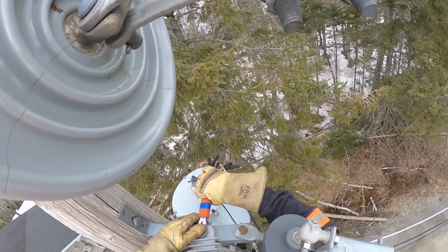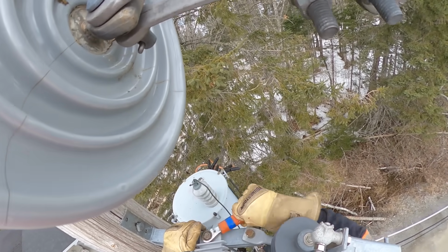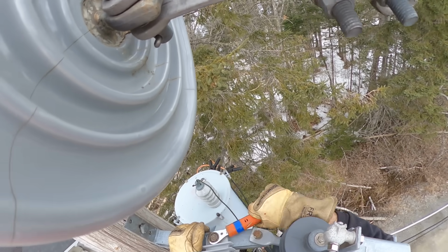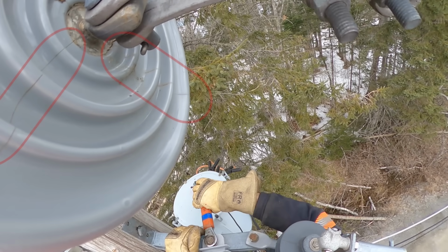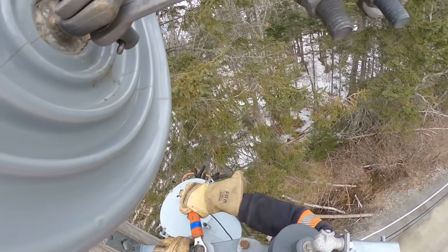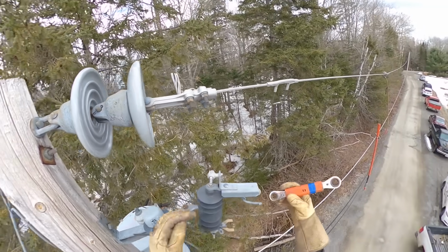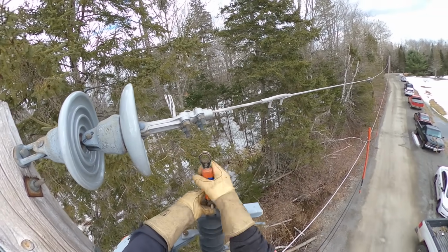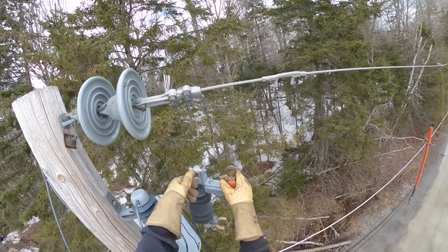Those poles just kind of dry up and shrink up a little bit sometimes. So there, I'm going to pause the screen here just for a sec. But you can see the cracks. There's 2 cracks. Eventually that would completely fail. If the second bell was cracked like that, those guys would have blown apart. For 7200 volts, you do only need 1 bell. The second one is just an overbuild. So in the case that one does crack, it's not going to trip the line out.